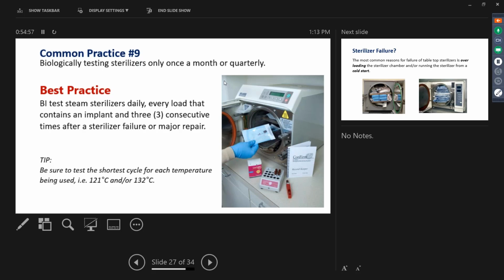So I usually tell the doctor or the nurse, when you have your sterilizer serviced, you should receive a document saying it passed this test. Of course, they're going to test it in an empty sterilizer, and then you should immediately test that day in your full load. Which load of the day? Picture in your mind's eye what your largest load is for that day, that's the one I'd recommend you test, worst case. From a regulatory point of view, you need to test; from a science point of view, it's great if you test in worst case. But I'd much rather have that conversation than explain to somebody why they're not spore testing at all, which is usually the case.